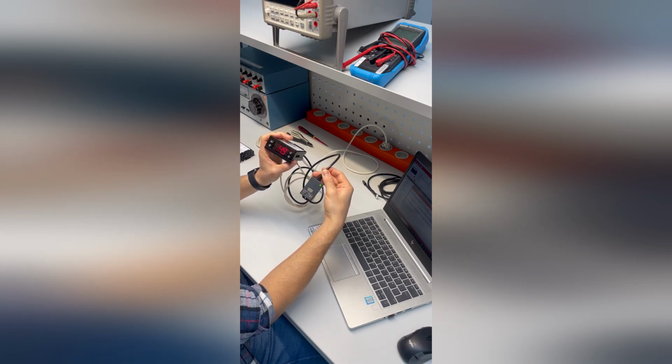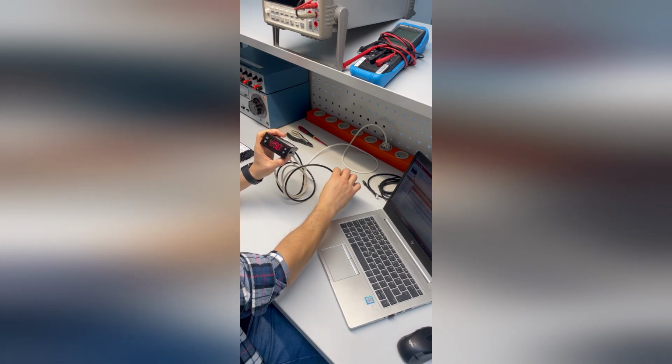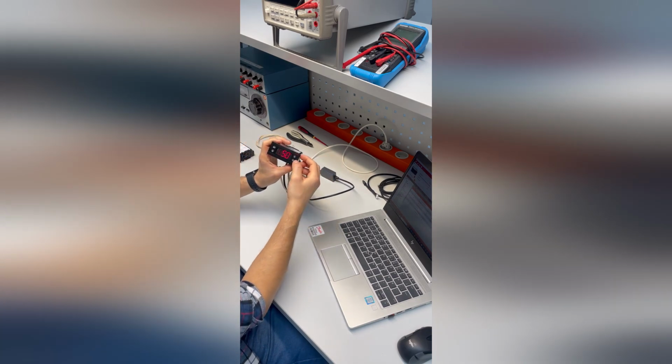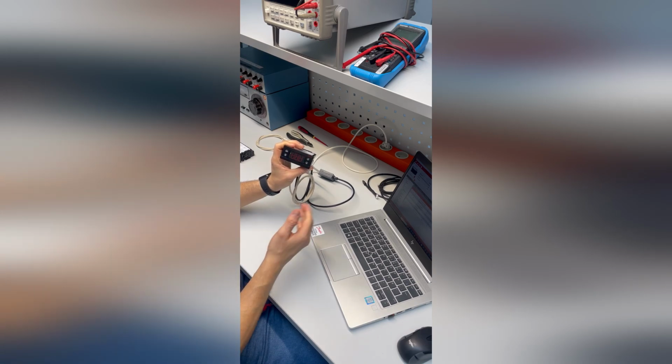So let's just confirm if the temperature, the set point is correct, so then we confirm that the database was downloaded correctly. So here it is, the set point as 10 degrees, just like we have just done here in our Koolprog.